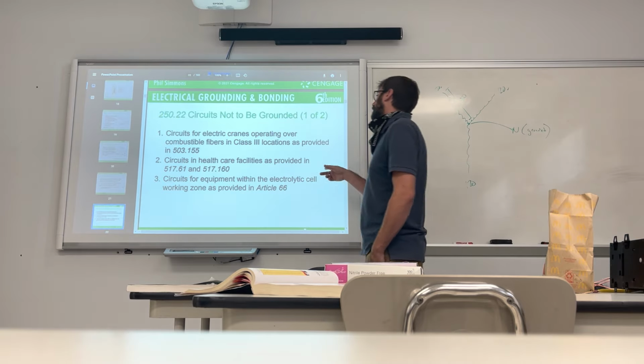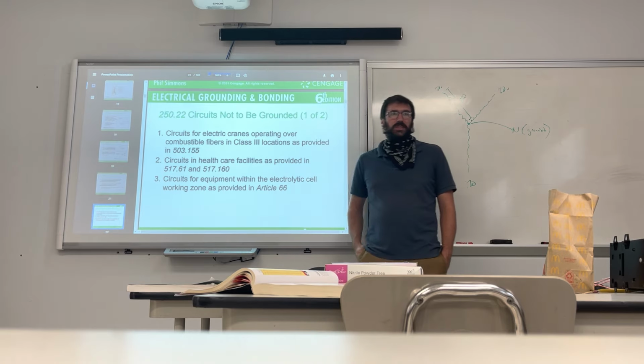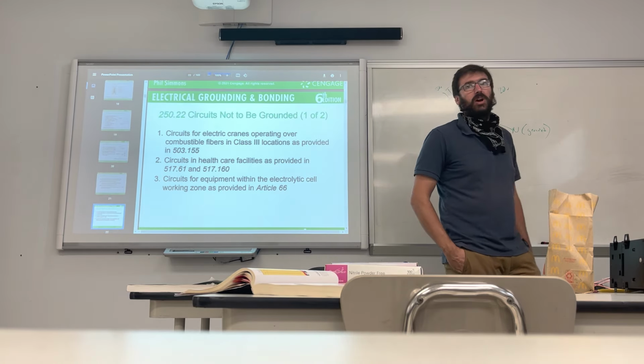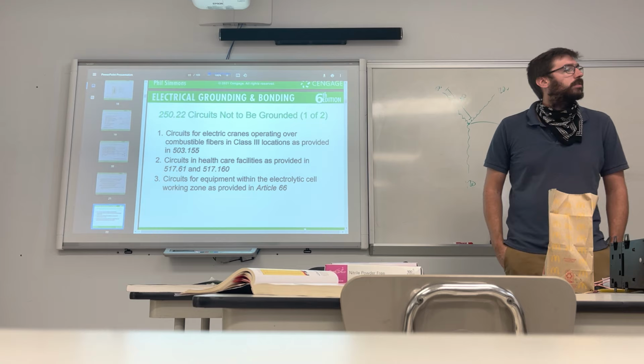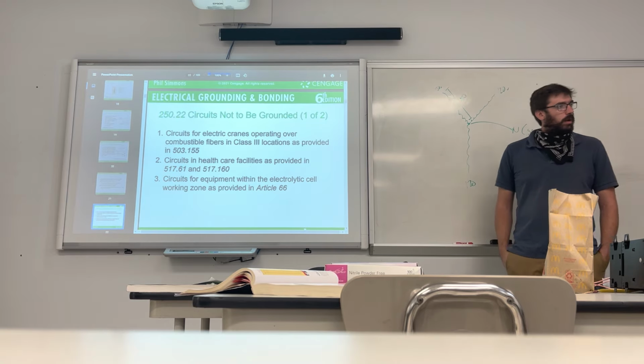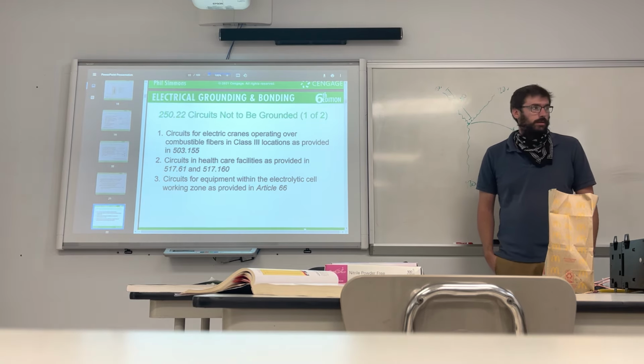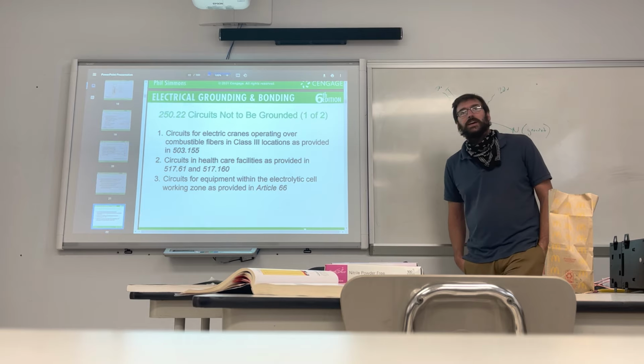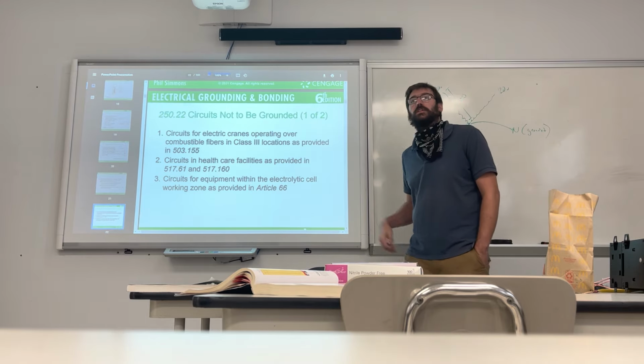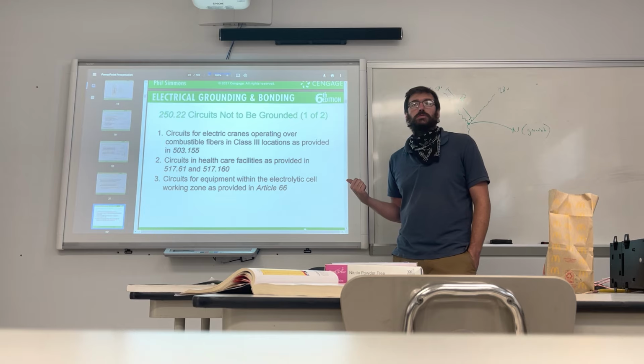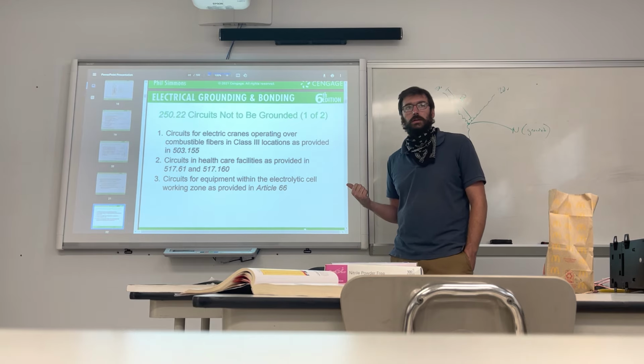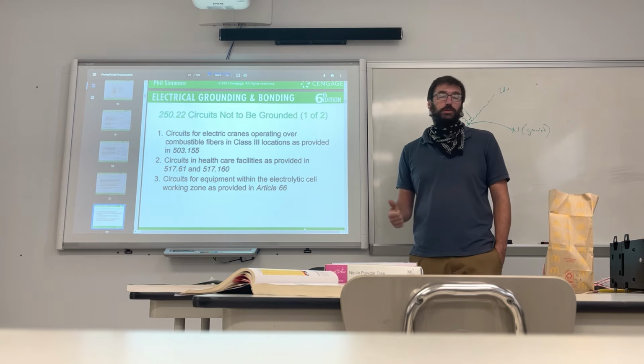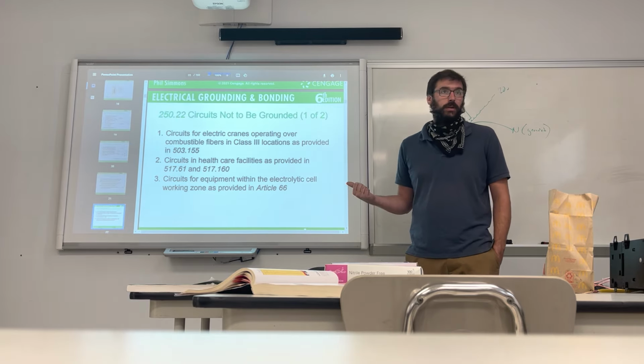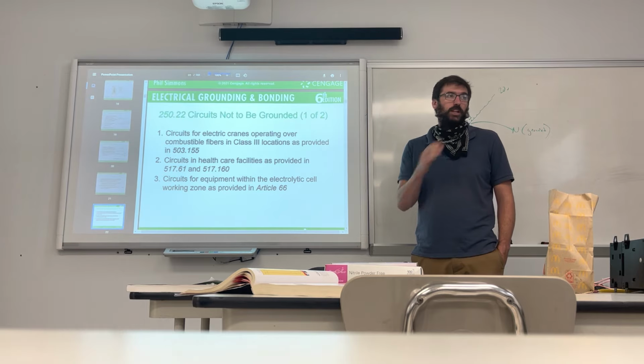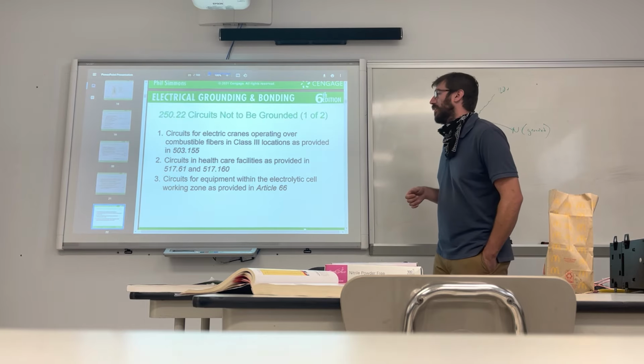But circuits in healthcare facilities, what is up with that? This is healthcare. People could get hurt. Why in the world would you want an ungrounded system? Because if it's something that has to run continuously, like life support, you don't want it shorting out. Yes. Your ground was intended to save people, but if something grounds out, and the machine moving that person's lungs just shuts off, what's going to happen to that person in 2 to 3 minutes? The answer's dead, in case you were wondering.